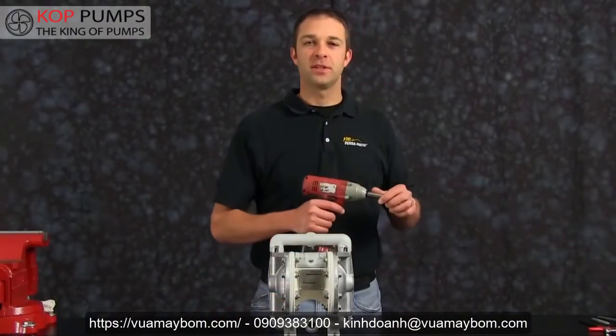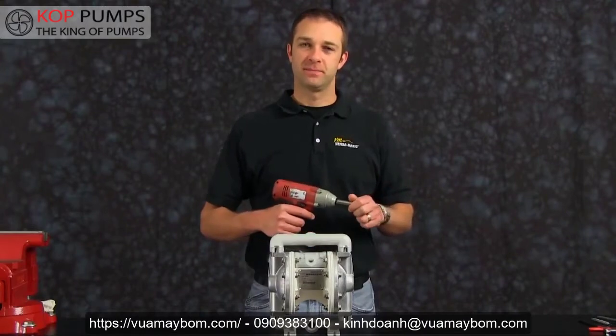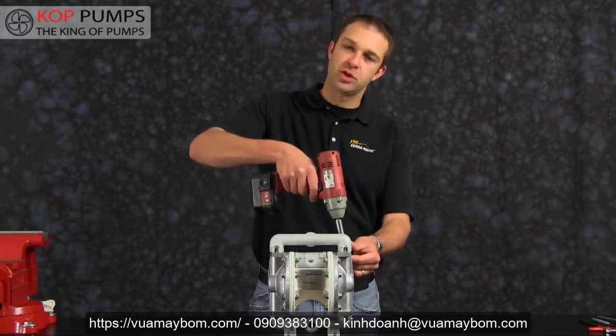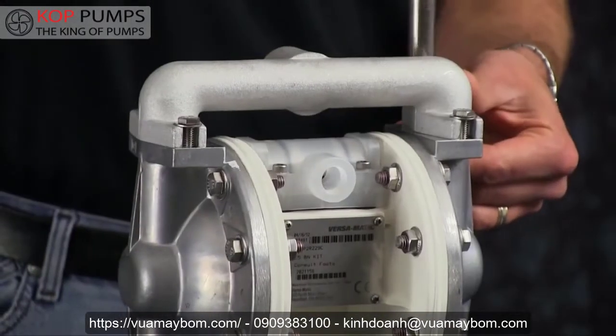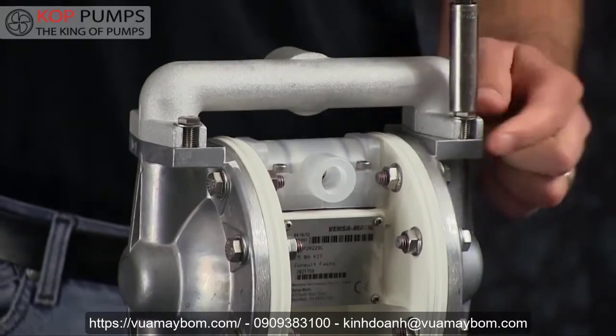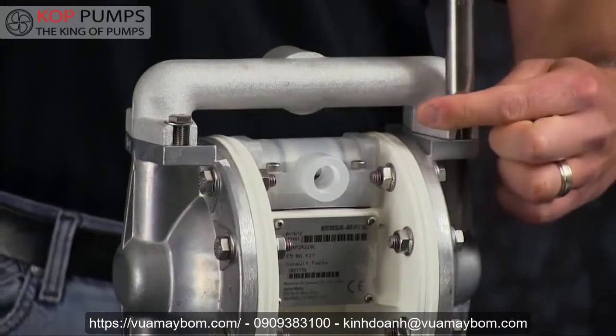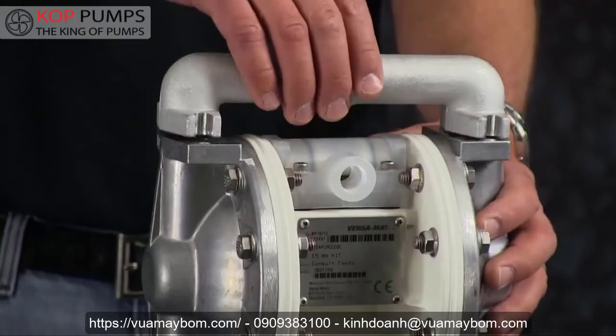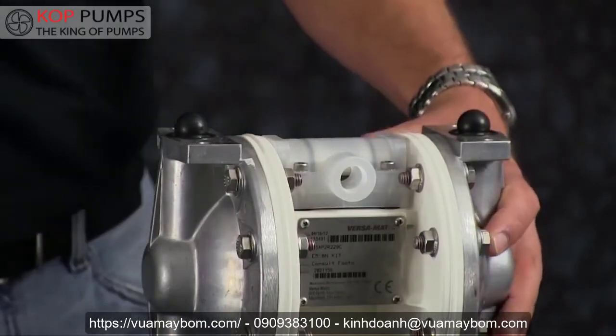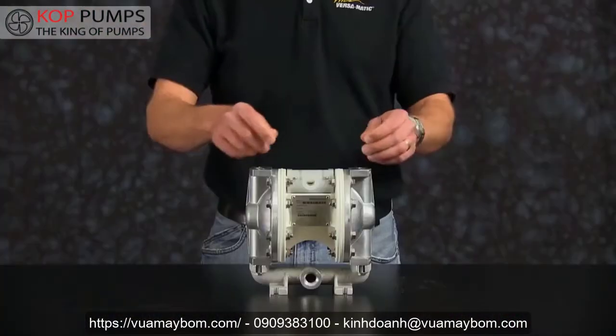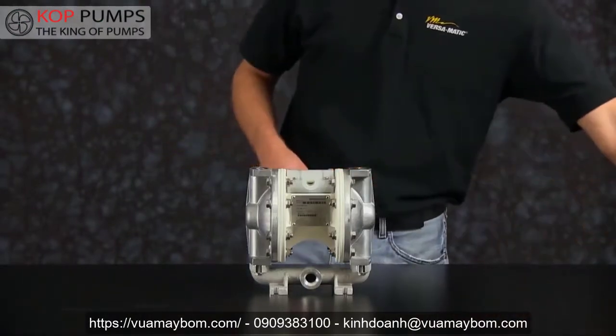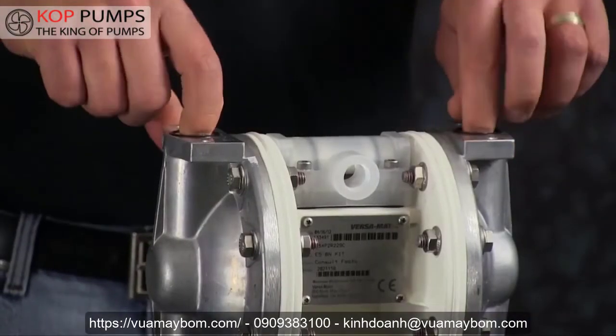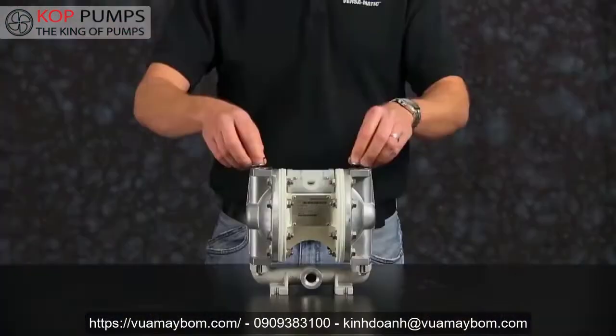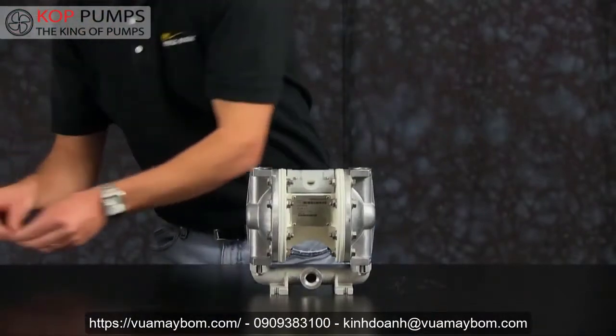Today we're going to use a 3/8 impact gun for ease of maintenance. Let's remove the discharge manifold. Remove the discharge manifold and set aside for later rebuild. Remove the discharge check balls and discard. Remove the valve seats and the valve seat O-rings. Be sure to discard the old valve seat O-rings.